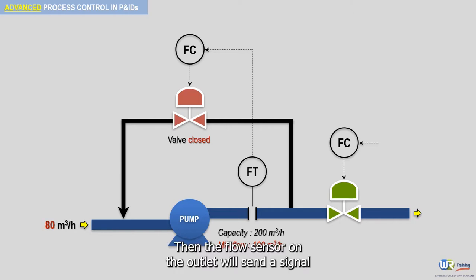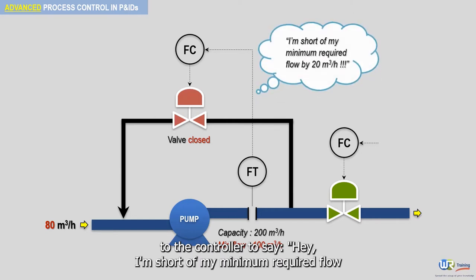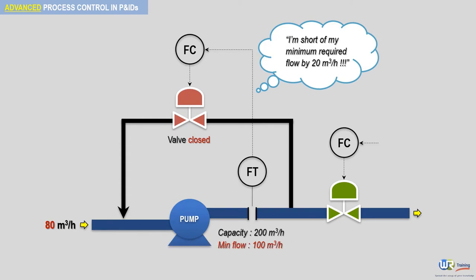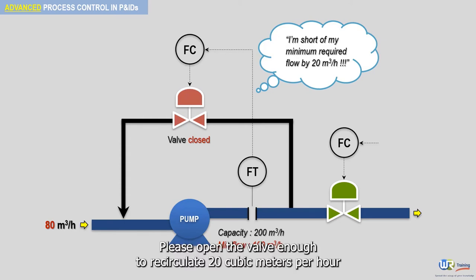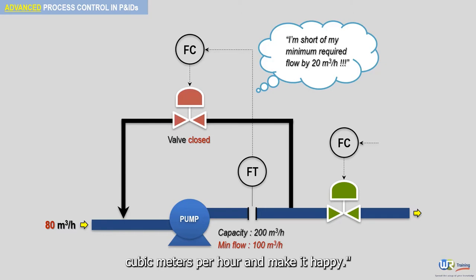then the flow sensor on the outlet will send a signal to the controller to say: I'm short of my minimum required flow by 20 cubic meters per hour and I'm worried about the pump. Please open the valve enough to recirculate 20 cubic meters per hour so we can fool the pump into thinking that the flow is 100 cubic meters per hour and make it happy.